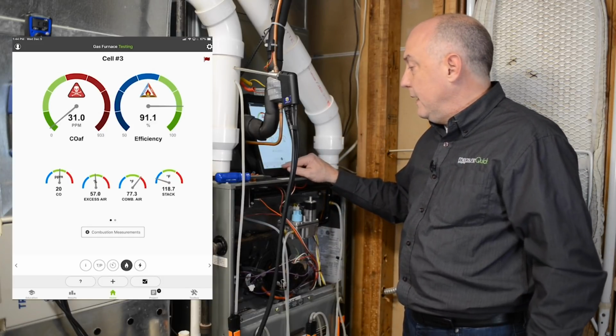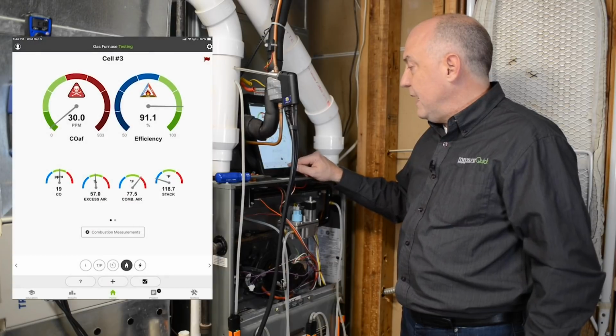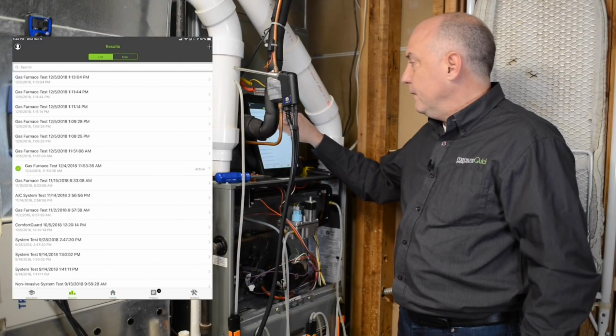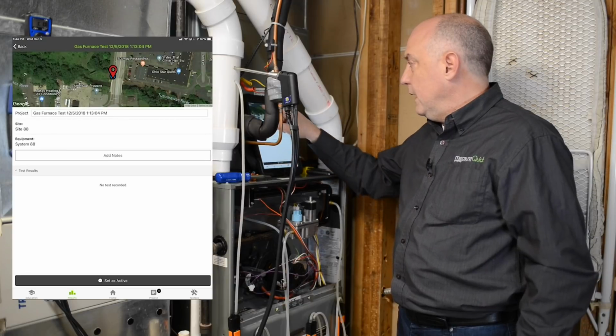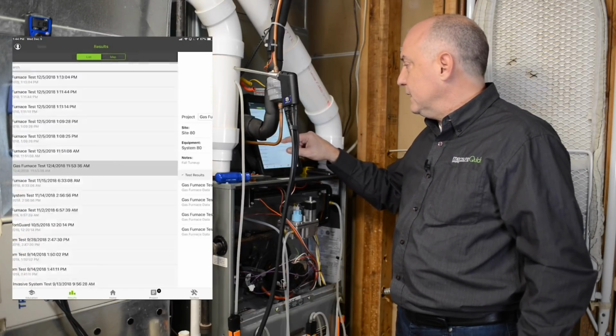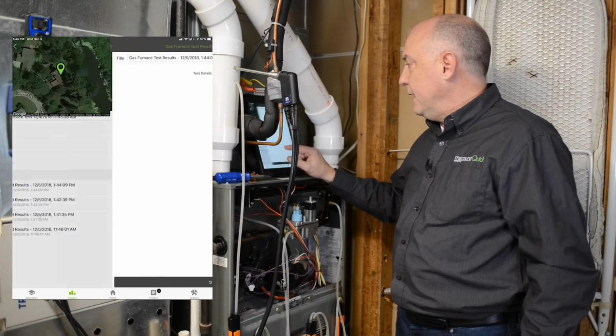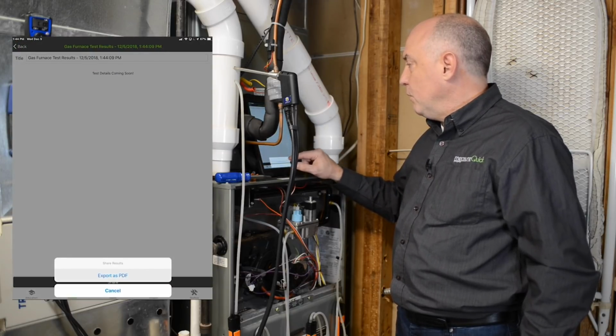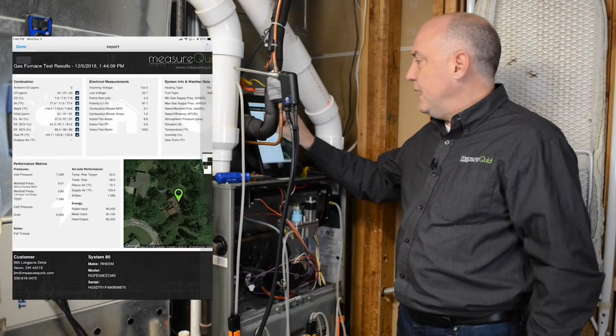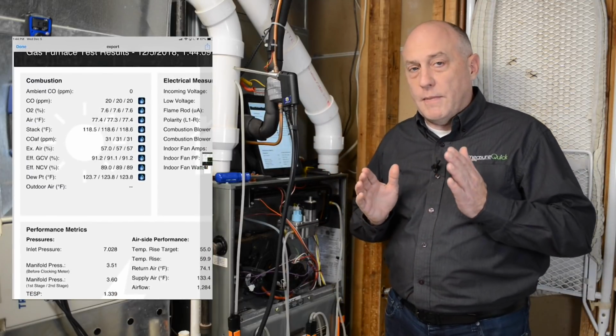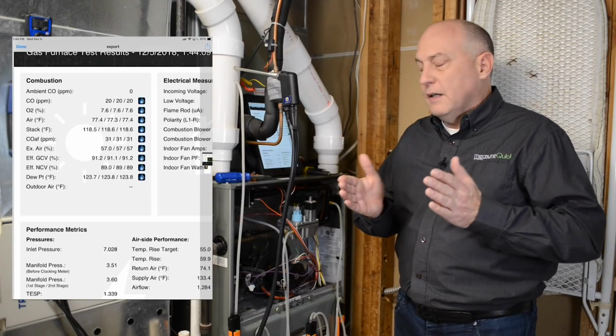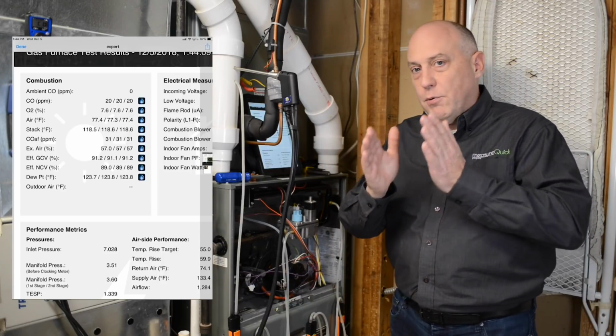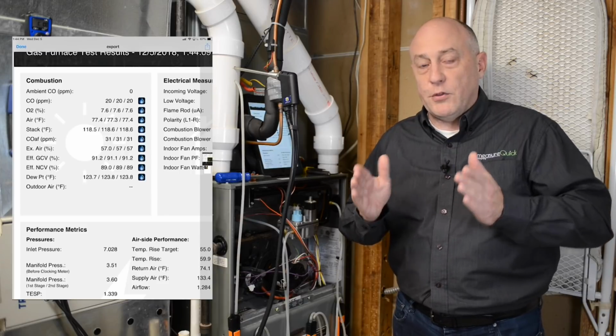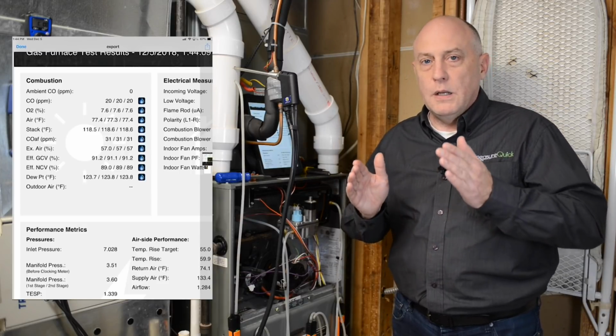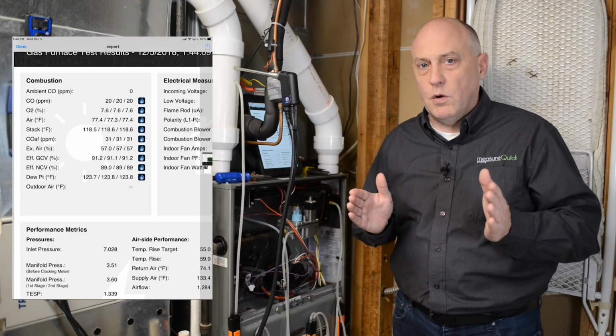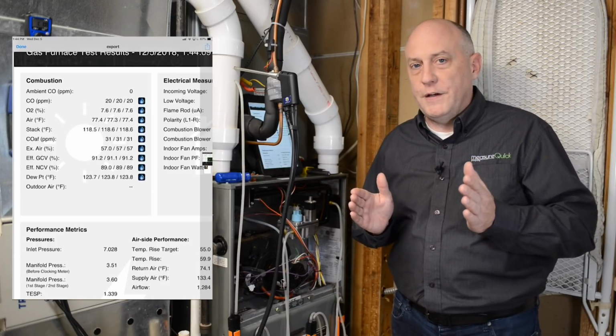So let me go ahead and we'll just save that, save the snapshot, go back into results here, and let's see if that one, oops, I got to go back to the active test, and we'll look at the one that we just shot here. Share, export as PDF. And now you can see when we zoom in on that I have all my combustion analysis measurements for all 3 cells. Obviously we're checking the same stack on here, but you can see it pulled in all 3 readings. So now I don't have to print out 3 combustion tests for the appliance on here. I can do up to 6 cells on one furnace and get them all in at once. So again, another really, really powerful, cool feature of the application.